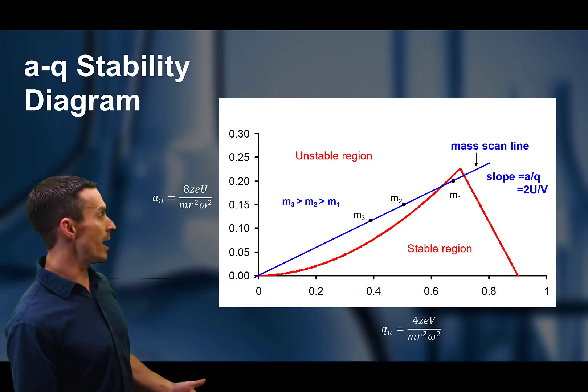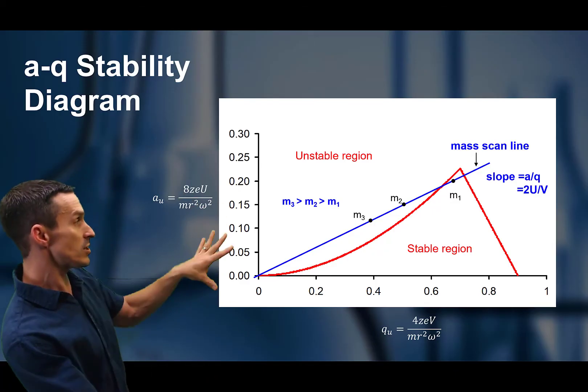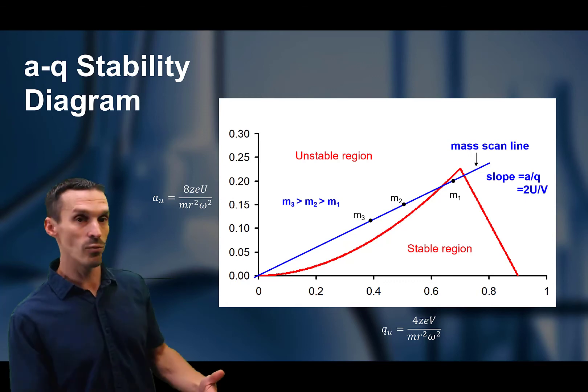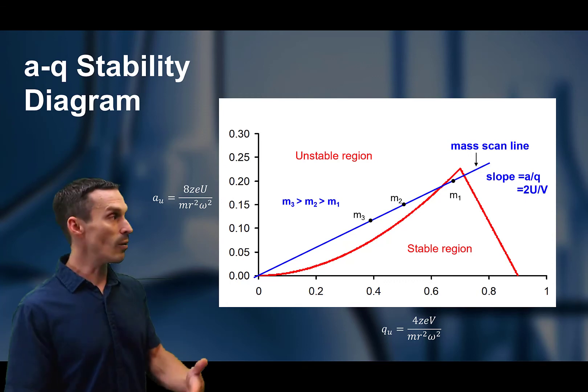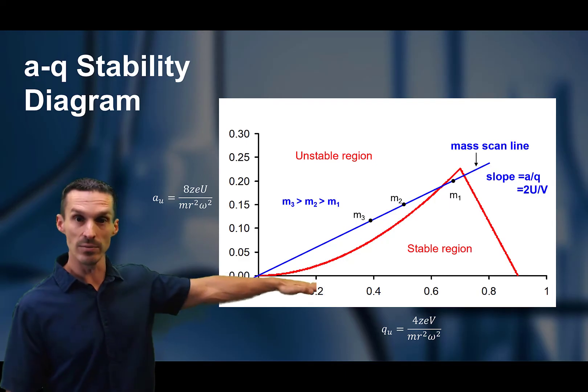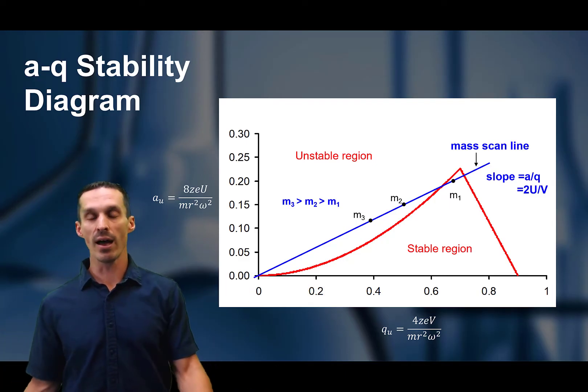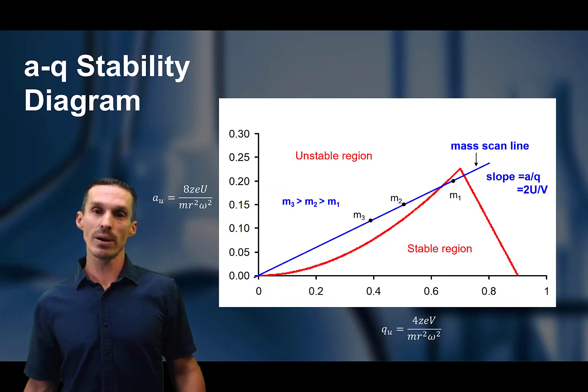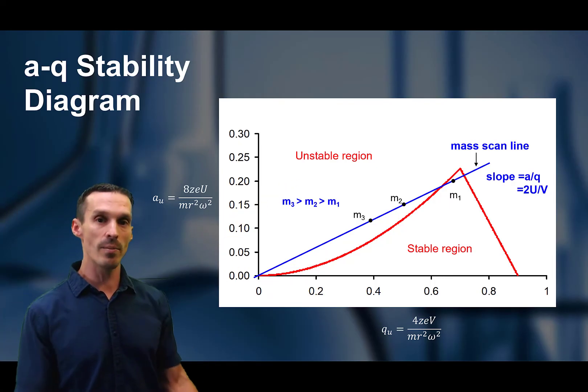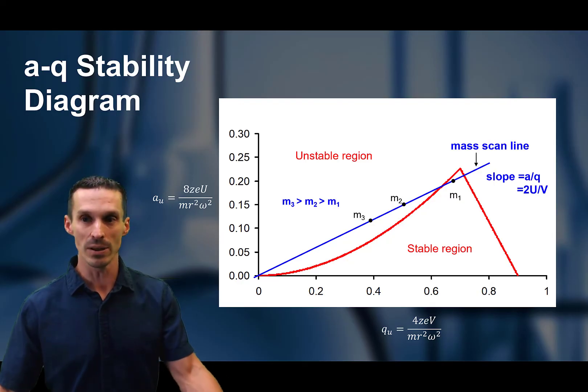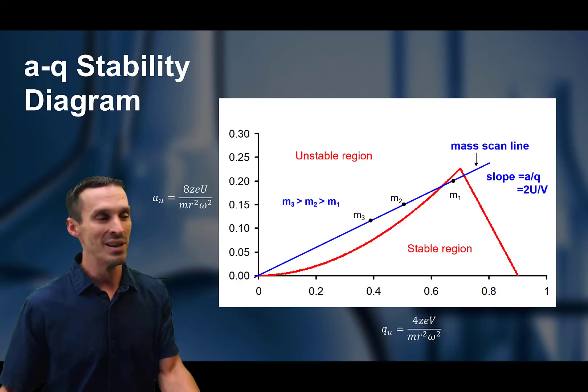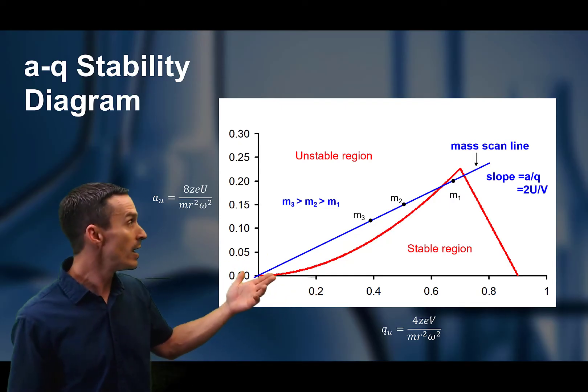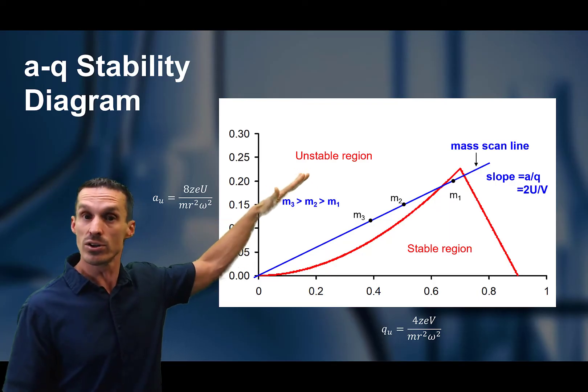So any ion with its given m over z will land somewhere inside of this plot, and that depends exactly on how you decide what voltage to set. So what is the magnitude of U and of V? So we pick that, and when we pick that, what we do is we fix it just onto that line. So that blue line is what we call a mass scan line. Those are the parameters that we define when we turn on the instrument. Now by the way, when you operate a mass spec, the instrument's doing this for you. So you're not having to type these numbers in, but this is what it's actually doing—it's placing all of the ions on this virtual line.